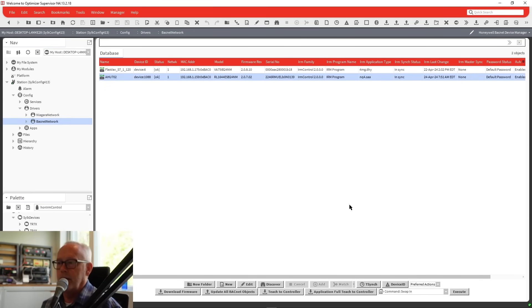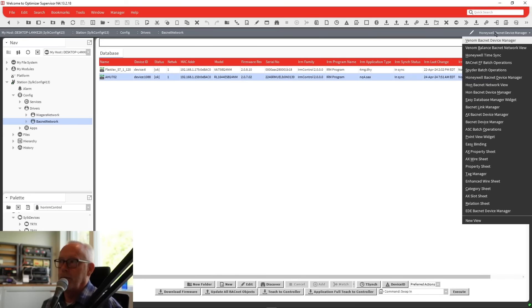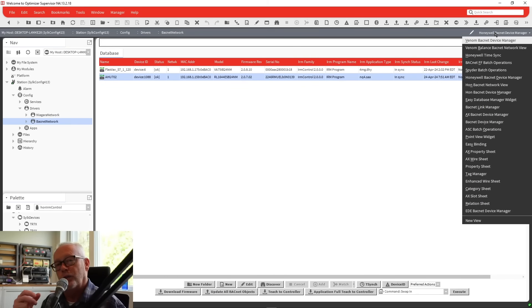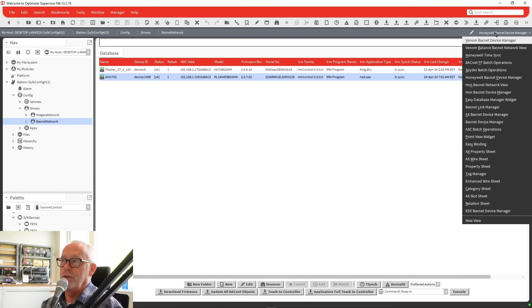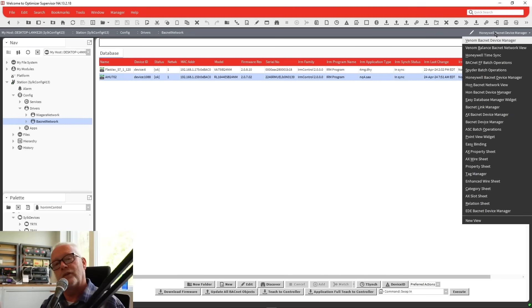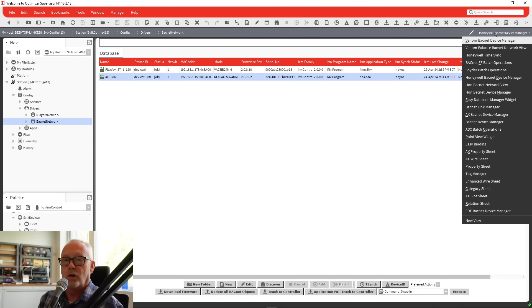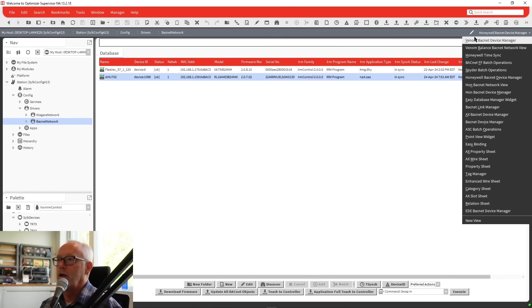The main differences are: no more separate IRM device manager. Also, there used to be a TC thermostat manager for the TC 300 and 500 thermostats — that has been incorporated underneath the Honeywell BACnet device manager as well. So if you're looking for TC or IRM, it's now the Honeywell BACnet device manager.